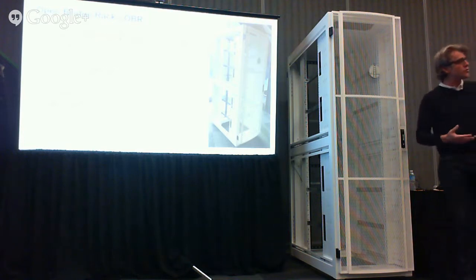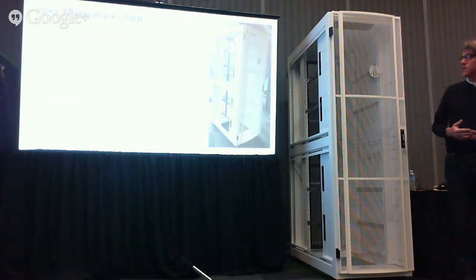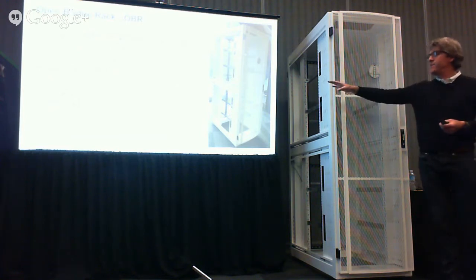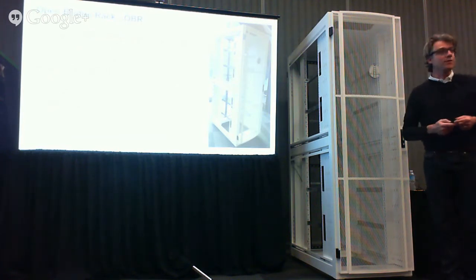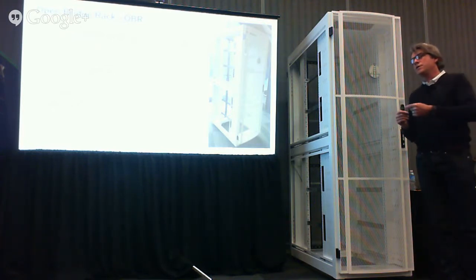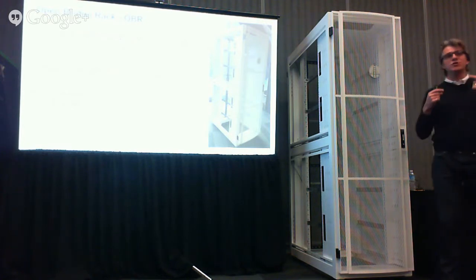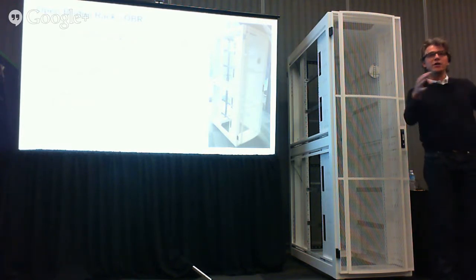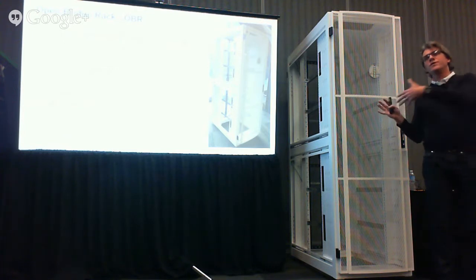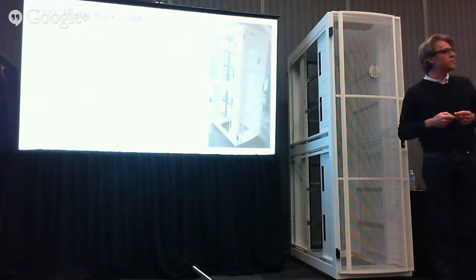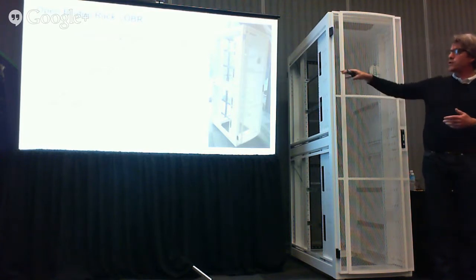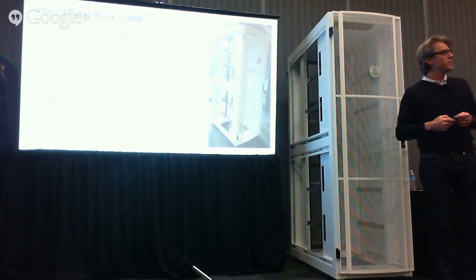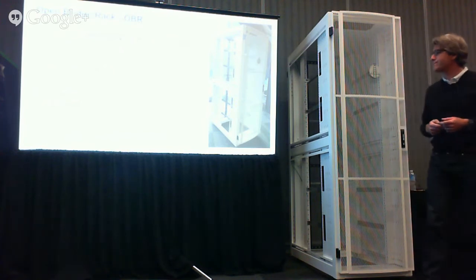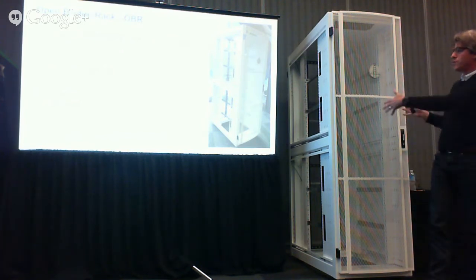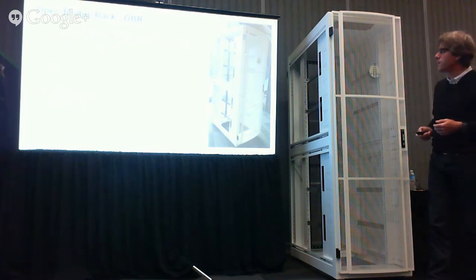In terms of the structure of the rack, it's capable of 1,000 kilogram dynamic load and 1,350 kilogram static load. With the open bridge rack, the assumption for a lot of customers is that racks will be on site and they'll bring IT gear to populate inside the rack, so having a rack with that range of capacity makes sense. This is where we are with the standard frame design.